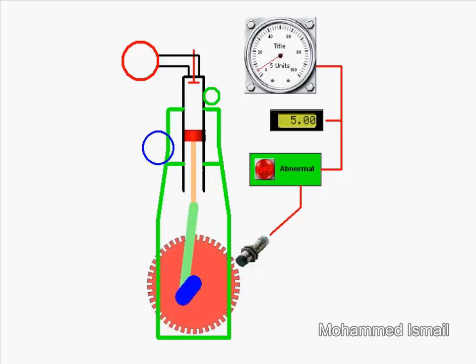In the demo, initially during starting the main engine turns one turn by slow turning control valve and then goes to full starting speed by opening the main air start valve. The demo also shows if the main engine cannot make a complete turn due to hydraulic lock, then the engine startup is aborted and a failure alarm is sounded to inform personnel to inspect the cause of starting failure.